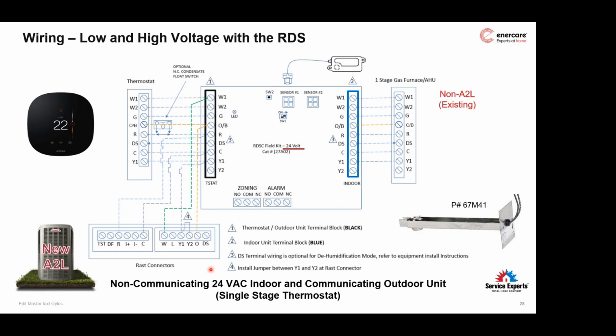67M41. It's just a 2-wire temperature sensor that goes into the discharge airstream and basically controls the fossil fuel coming on and what temperatures it's allowed to ramp up to. I believe somewhere between 70 and 90 degrees is the on and off for this temperature sensor. It basically just provides enough heat in the air that it doesn't feel like it's frigid during the defrost cycle. All that little sensor would do is break that W signal between the outdoor unit and this indoor control board.